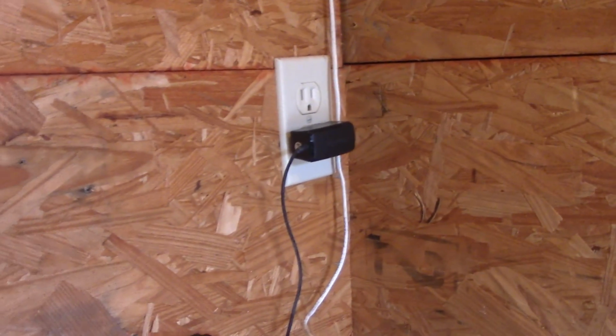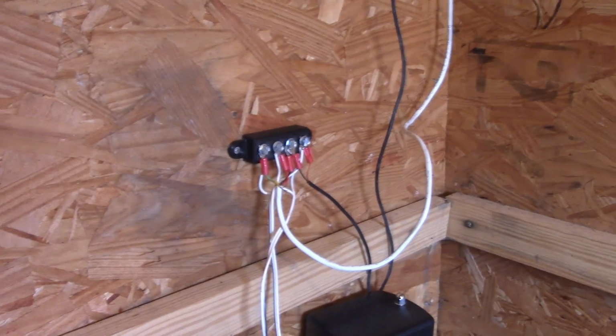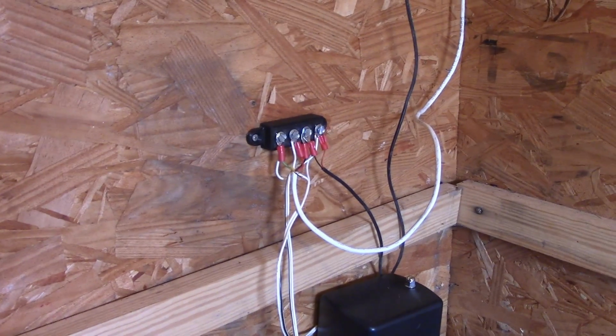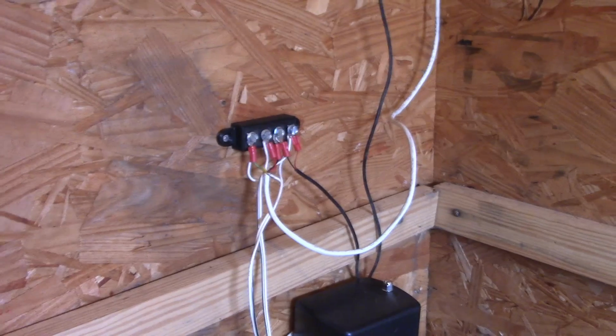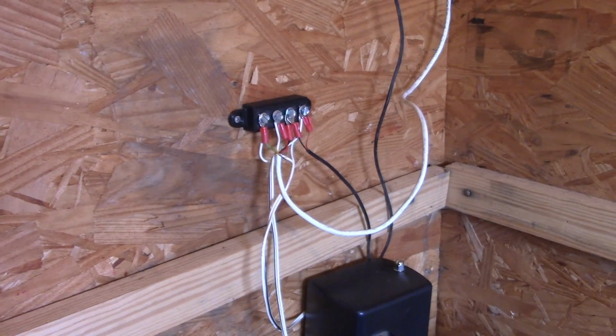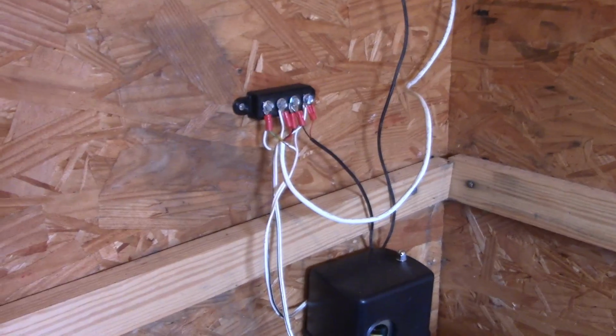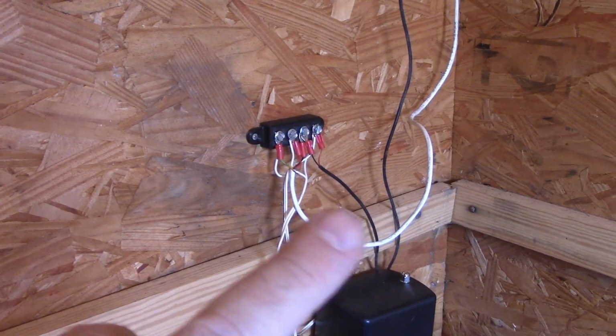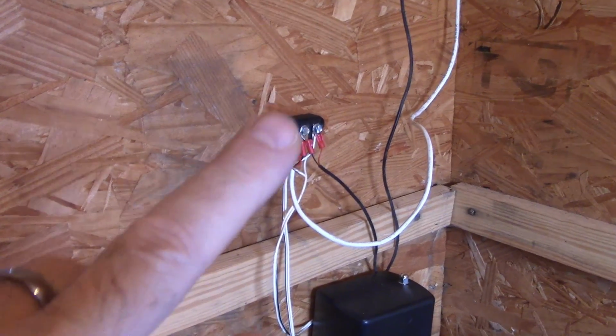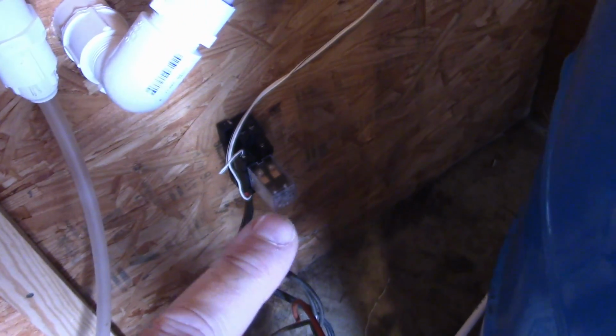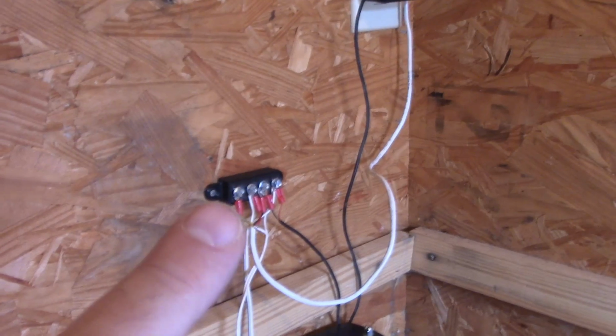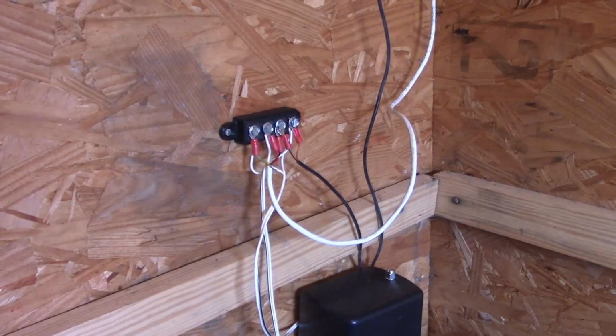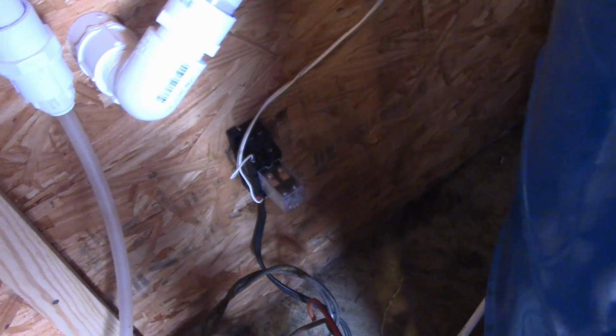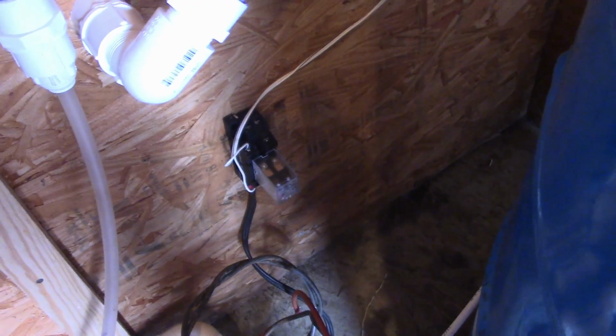Now, it's just run off of a 5-volt phone transformer. And so what you would need to do is get you an indicator light. And I'll list some in the description of this video for you in case you're interested in that. But say in this instance, you would get a 5-volt indicator light that's a bright light. You mount it on the outside, so what happens with this is you've got 5 volts that comes from your transformer. You send one leg to that indicator lamp. Then the other leg of the 5 volts is going to go down to your relay and get switched by your relay and back up to this terminal block, and then it goes to the other side of your LED and your LED lights up. So every time your pump comes on, it triggers this relay, which then lights that LED, and so every time your pump runs, you can see that visually on the outside of the building.